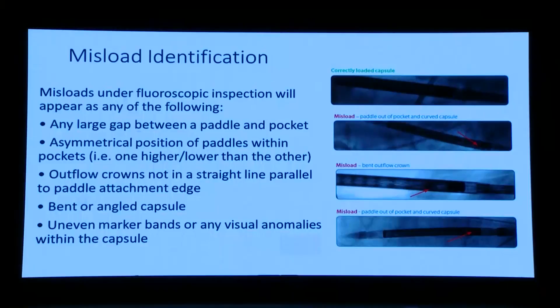So that's again to clear. If we do fluoroscopy and a cine run, and there is any asymmetrical position of the paddles within the pockets, or any bent or angled capsule, uneven marker bands, anything like that, we know that it's improper loading. The loading is usually done by the team from Medtronic, and we check whether it's loaded properly by doing a cine, rotating the catheter 360 degrees, doing a cine, and replaying it again to make sure that it's loaded properly.